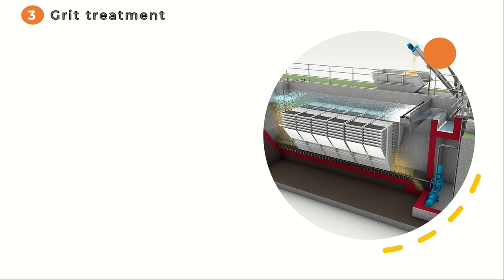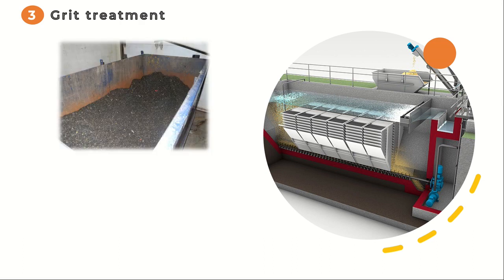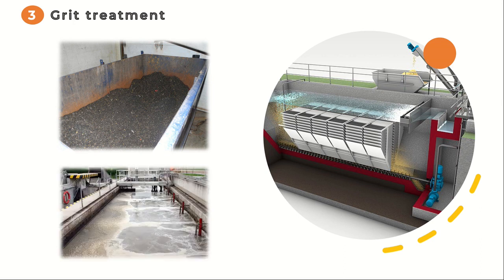The third step involves grit and sludge removal, a very important step in the wastewater treatment plant. The wastewater flows into sedimentation tanks where heavy particles such as sand and grit settle to the bottom. The aerated grit trap's task is not only to reliably remove the grit from the wastewater flow, but also to retain grease to prevent floatable particles from settling or overflowing in downstream treatment systems.